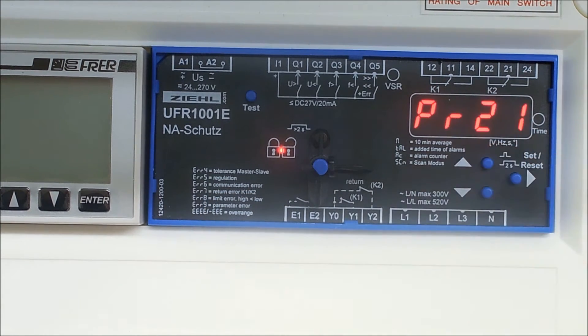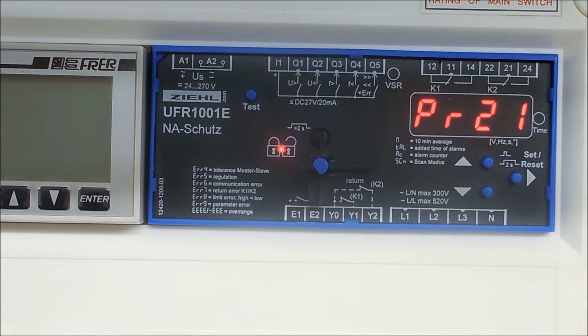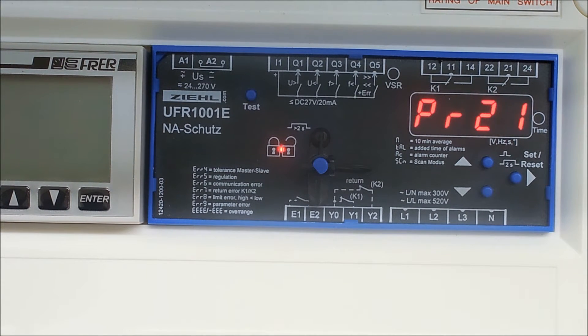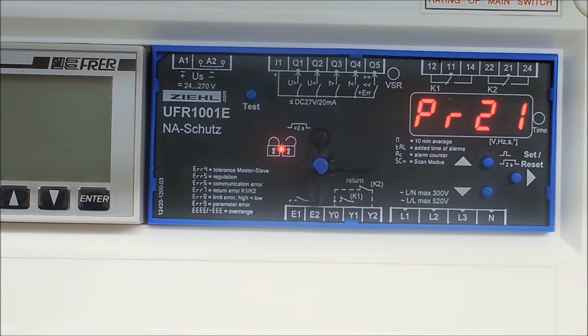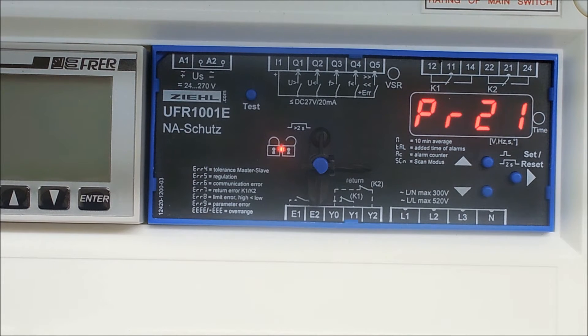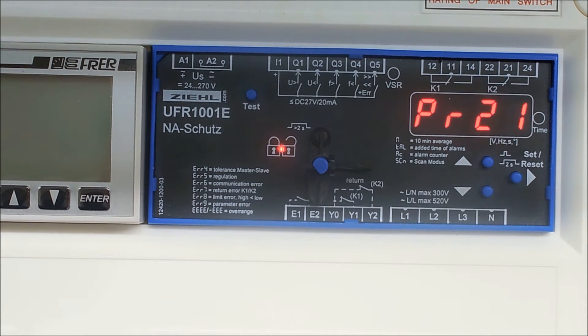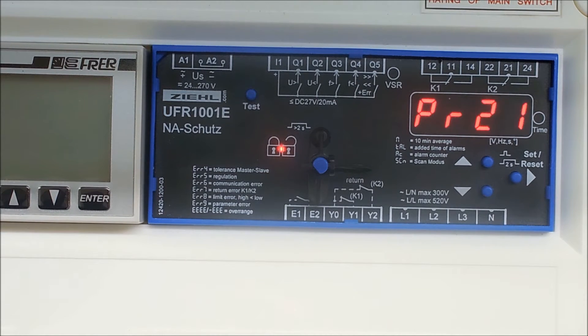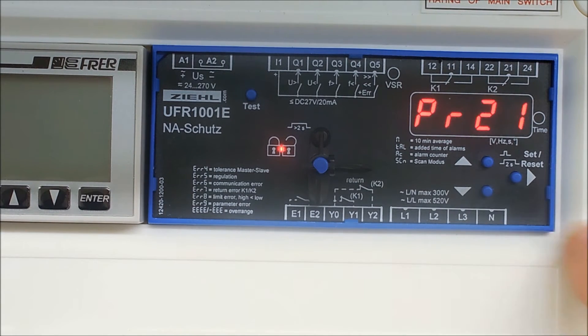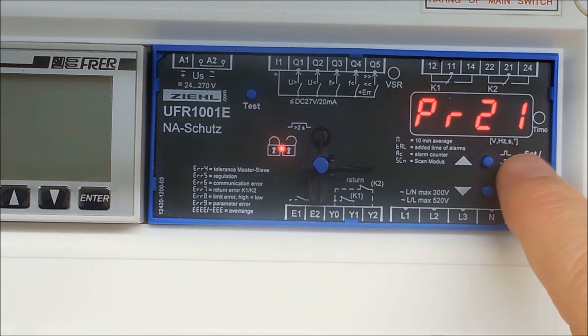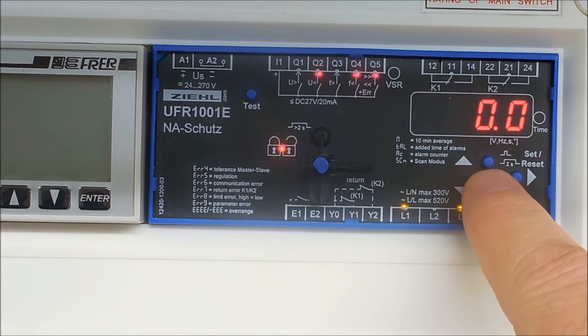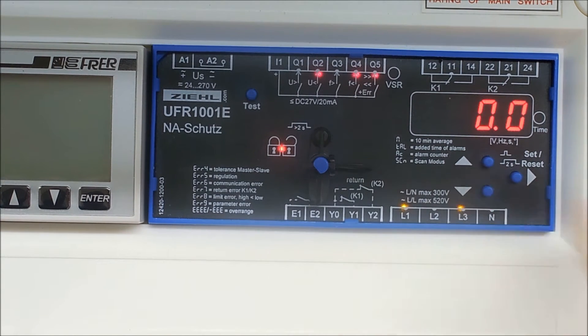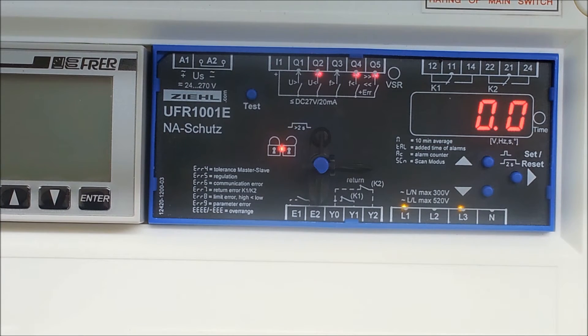Then you have the program. The program is important. For this unit you have predefined as per the G59 3 standards the values set and defined in the standards for 3 phase 4 wire, 3 phase 3 wire, 3 phase VT 57.7 volts and 3 phase VT 100 volts. Those are the values, time delays, everything as defined by the standards pre-configured in the unit. New info again and then down and let you back to the start of the menu. Next we'll look at how to program the unit.